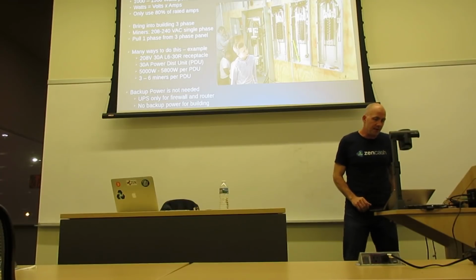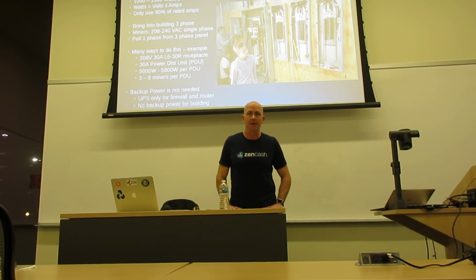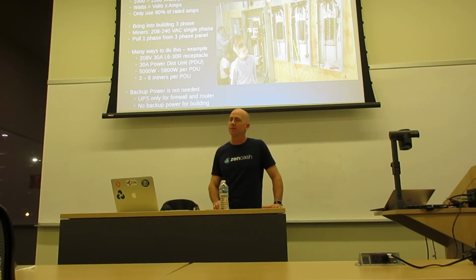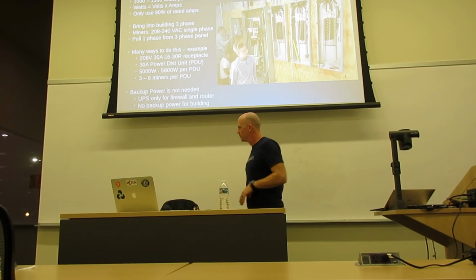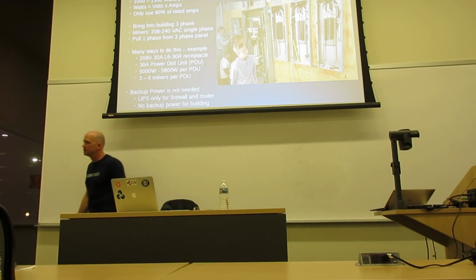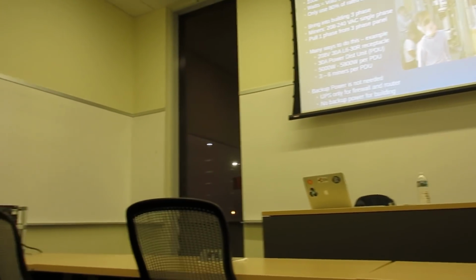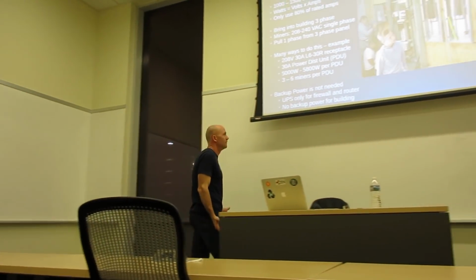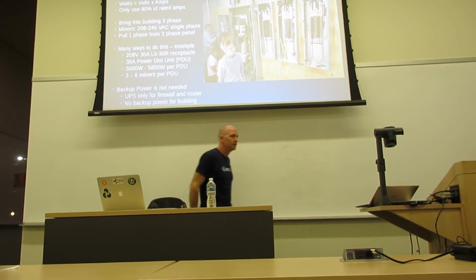Okay, so there's a lot of electricity. Here's my son checking out half of our existing electric build-out. This does about 250 kilowatts. The electricity comes in at 208 volts, three phase, 1200 amps, and it gets split out, and then we pull single 30 amp. I'm actually a little surprised I didn't trip a breaker here, because if I plugged a second one of these in, it would trip the breaker. These things use a lot of electricity. That's just the way it is.